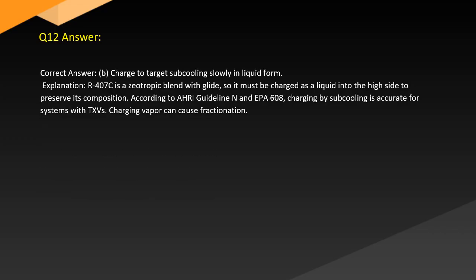Answer. Correct answer: B. Charge to target subcooling slowly in liquid form. Explanation: R407C is a zeotropic blend with glide, so it must be charged as a liquid into the high side to preserve its composition. According to AHRI guidelines and EPA 608, charging by subcooling is accurate for systems with TXVs. Charging vapor can cause fractionation.